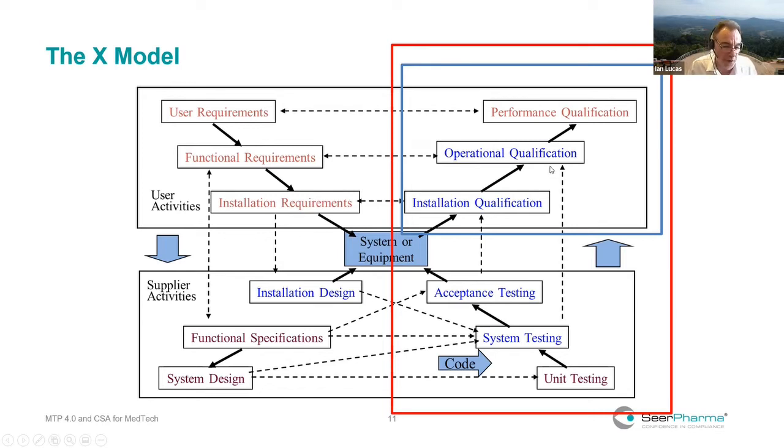And we qualify processes, we qualify people. It's taking what you've got at a point in time and making sure that they're fit for purpose. That's what qualification is. Whereas testing is looking underneath the hood a little bit as well, and looking at the coding standards, etc., making sure it's been followed, and those sort of things. When it gets up to qualification, you just assume that those things have been done.